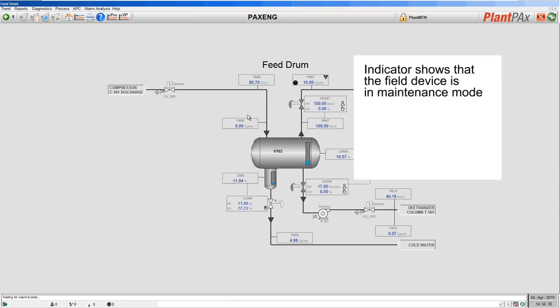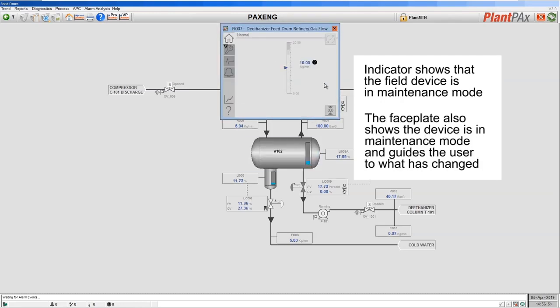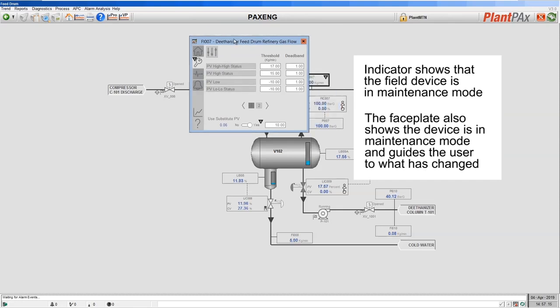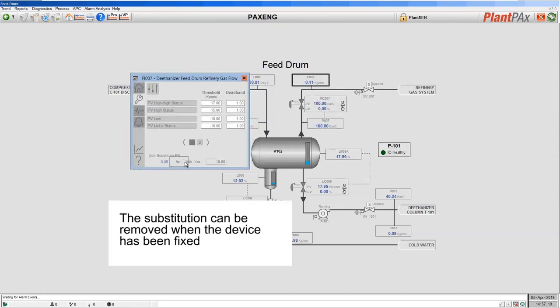Now as an operator coming to the HMI, I can notice straight away from looking at the graphic that something is not normal with the analog input. A question mark is shown to indicate it's being substituted, and there's also a spanner symbol to say something's not quite normal. By clicking on the HMI symbol I can bring up the full faceplate and see that the spanner symbol is shown on the maintenance tab, indicating where something is not normal. On the maintenance tab the spanner is highlighted against the substitute switch, showing that the value is currently being substituted. I can remove the substitution by selecting the switch, and the maintenance symbol is removed. We call this the breadcrumb trail — it brings you to the location on the faceplate where something is not normal.